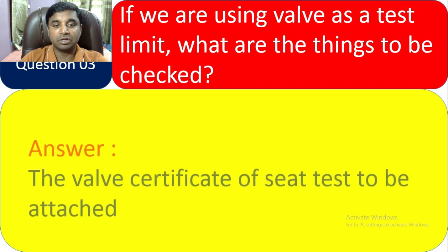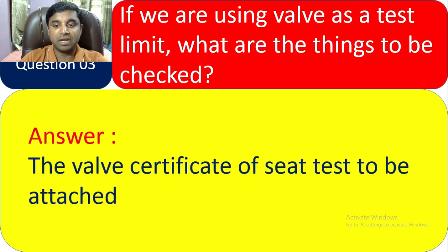Question 3: If we are using a valve as a test limit, what are the things to be checked? The valve certificate of seat test must be attached. You have to verify the valve certificate of seat test is mentioned as the test limit.